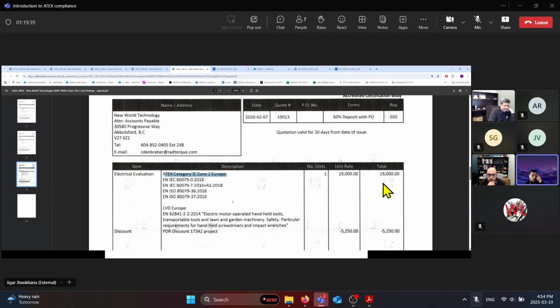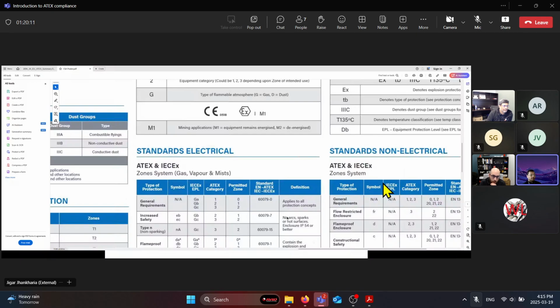But now if we're going to talk about zone 1 and zone 21, then that means that category becomes category 2, as well as zone 2 and zone 22, which will be category 3. But we still have the category 2 in that certification, basically, if compliant, right? So then that requires the quality assurance notification and report audit for IECEx and ATEX both. Okay. So that's the main difference, yeah. So it's basically determined off the zone requirements.